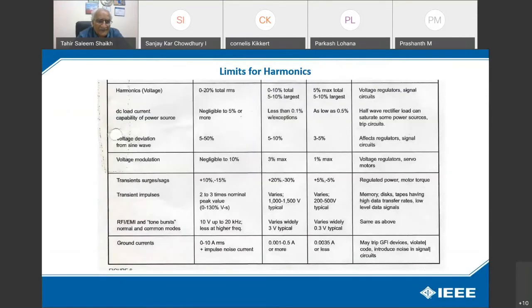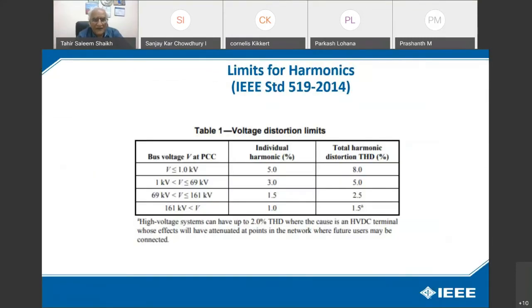So the transient pulses, ground current, how much should be the ground side leakage current, maybe the voltage deviation, how much in different environments. We are using electronic sensitive equipment. So 0 to 20% total RMS, 0 to 10%, 5 to 10% largest, and generally, we will come to that slide over there. 5% maximum total voltage regulator signal circuit is the solution for that. Now this is the IEEE standard 519-2014, which gives different voltage levels and the individual harmonic limits. Globally, multinational companies set their limits as per IEC and IEEE standards. So for the total voltage harmonics, the limiting value is 5% and the current harmonic is 10%.